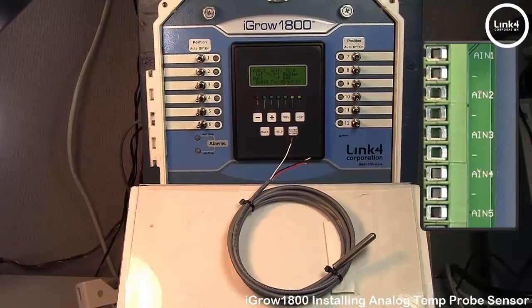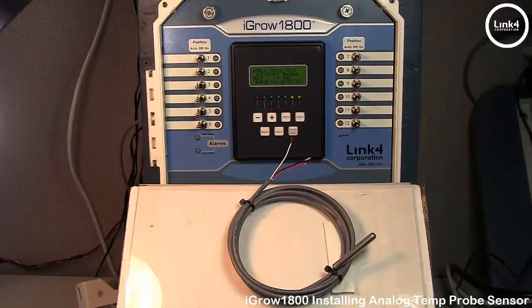and so forth. Now, the first thing you want to do is mount or hang your probe at your desired location. Next, run the free end of the sensor cable to the controller unit. Now, you may extend this sensor cable as needed, but make sure you use Link4 approved wire, and it must be shielded and stranded 24 AWG type wire.